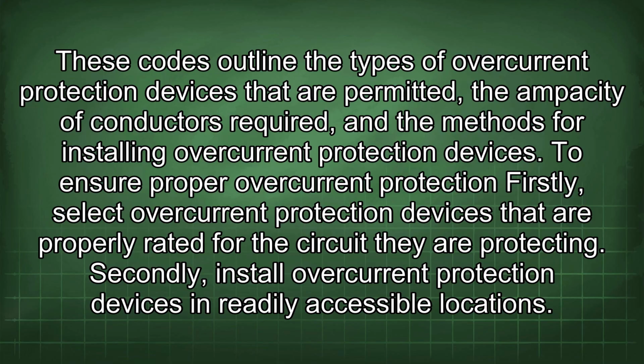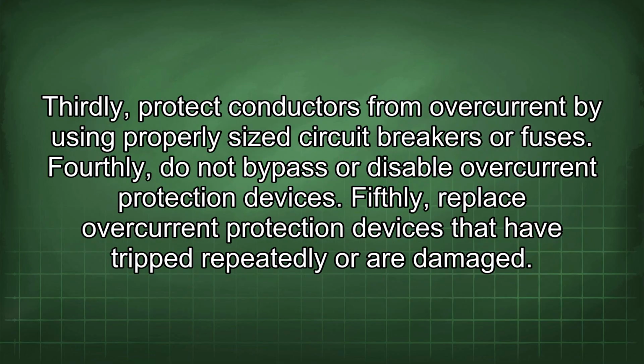To ensure proper overcurrent protection, firstly, select overcurrent protection devices that are properly rated for the circuit they are protecting. Secondly, install overcurrent protection devices in readily accessible locations. Thirdly, protect conductors from overcurrent by using properly sized circuit breakers or fuses. Fourthly, do not bypass or disable overcurrent protection devices. Fifthly, replace overcurrent protection devices that have tripped repeatedly or are damaged.